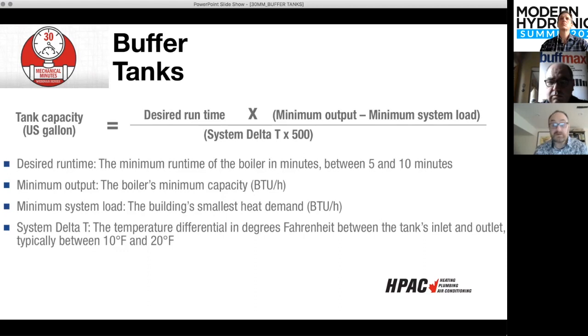We go through the math here. You've got your desired runtime, 5, times 20,000, which is your minimum firing rate, minus 2,000. So that's 10 times 500. And we divide that by your delta T times 500, where delta T is the minimum difference in your tank temperature that you want. You go through all that math, and in this case, with this very small boiler, we're looking at a buffer tank of 18 gallons, so a very small buffer tank. So it's all about doing the math, and the formula is right there.